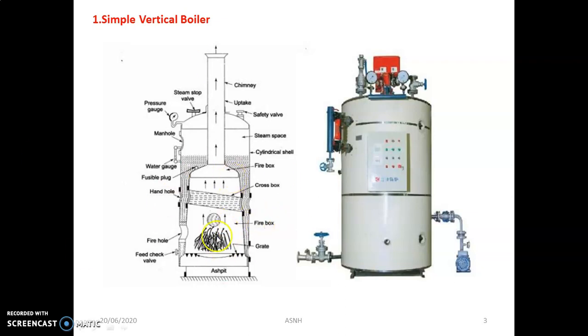The section above the grate is the combustion chamber. In case of the boiler, heat transfer takes place by all three modes. The most important is radiation, which accounts for around 70 to 80% of the heat transfer, followed by convection at 10 to 15%, and conduction at approximately 5%. So radiation is most important in the combustion chamber, where combustion of the fuel takes place.